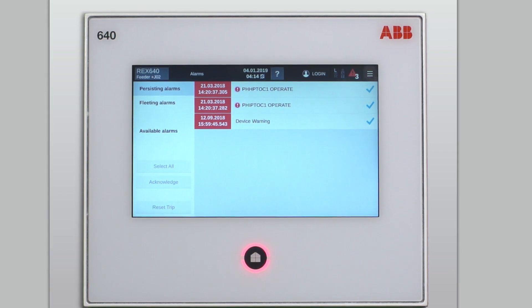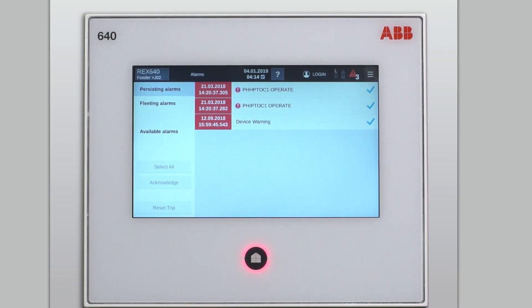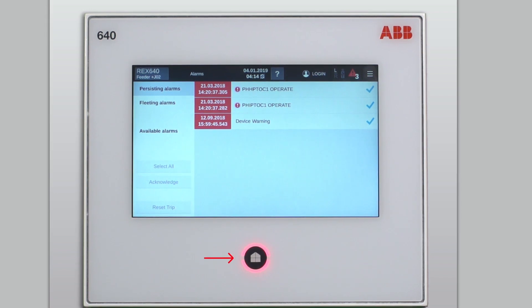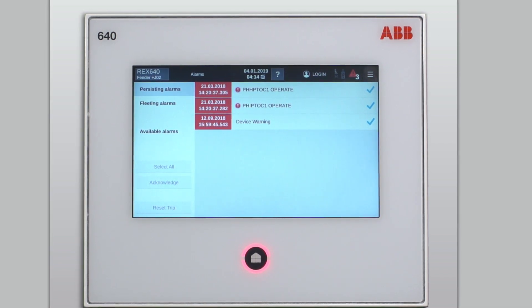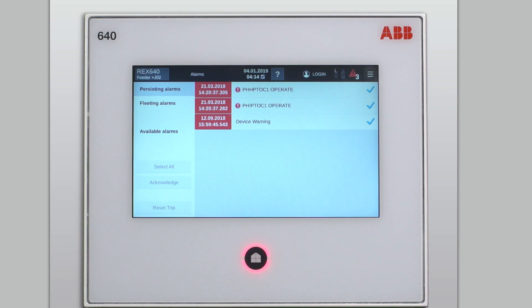But as you have now acknowledged those alarms, you can also notice that the behavior of the home button has changed. Now the home button is indicating a steady red light. This steady mode means that all the alarms in the relay have been acknowledged, but there are still some active alarms, as you can see from the page.